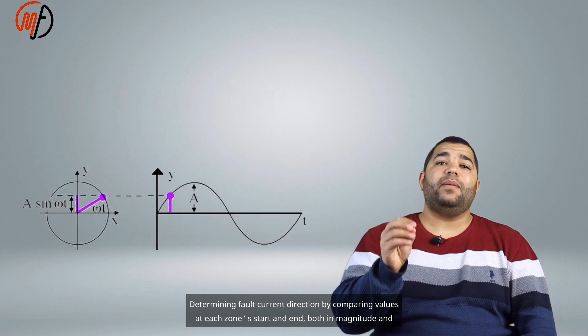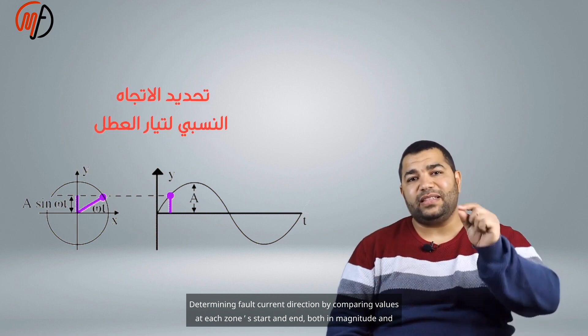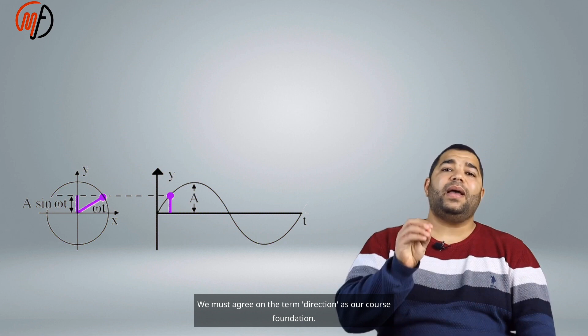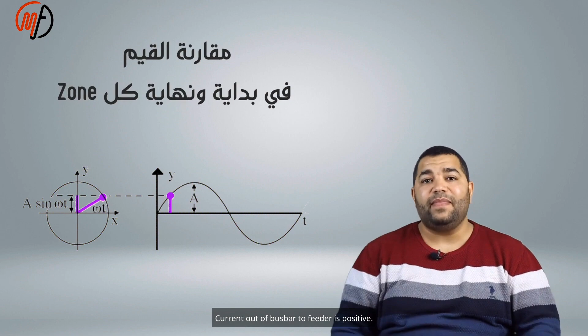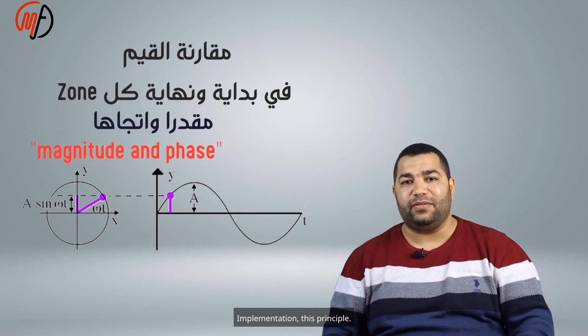Determining fault current direction by comparing values at each zone start and end, both in magnitude and direction, is key. We must agree on the term direction as our course foundation. Current out of the bus bar to the feeder is positive. Out of the feeder to the bus bar is negative.